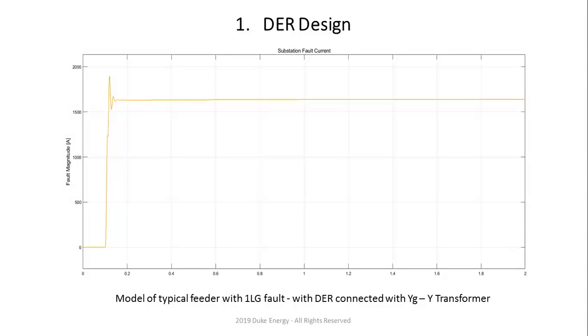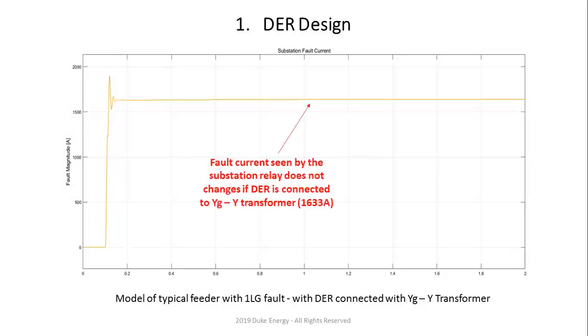Essentially, you have to change that particular transformer to the Y grounded Y transformer. And when you change it to the Y grounded Y transformer, the fault current seen by the substation relay does not change, right? Which is one major lesson learned. Also, if you take a look at arc flash analysis, the incident energy released at a particular site is 4 to 5 times higher than with a Y grounded Y transformer. So anytime you design this, just make sure you understand, if you put a Y grounded delta transformer, what is the impact on your settings, right?